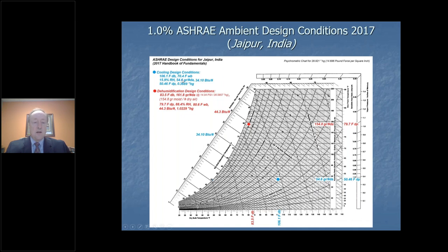The cooling point and the dehumidification point are both 1% numbers. That means there's 1% of the time that you're going to be above this particular number. So the number of hours are the same. So I don't understand why we spend so much time just on the temperature of the building and we don't pay attention to the moisture levels in the building. So here it is graphically on the chart to see what a difference it is.